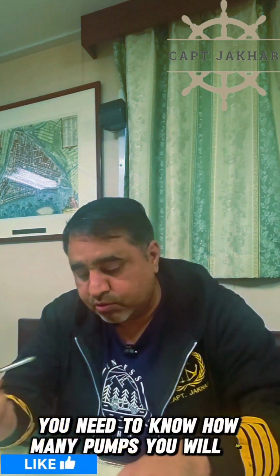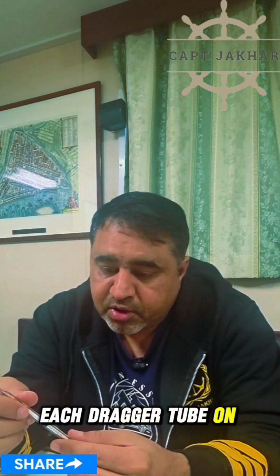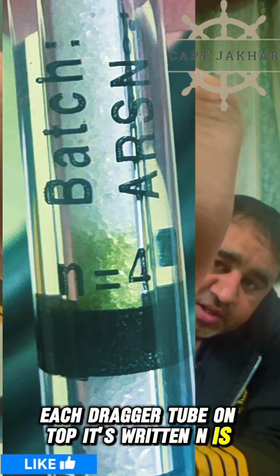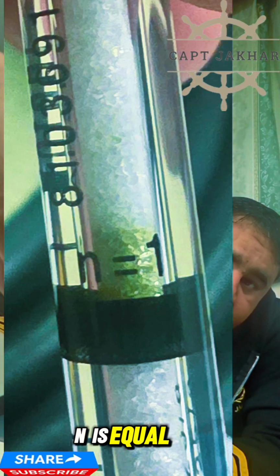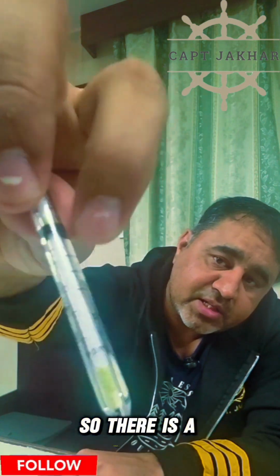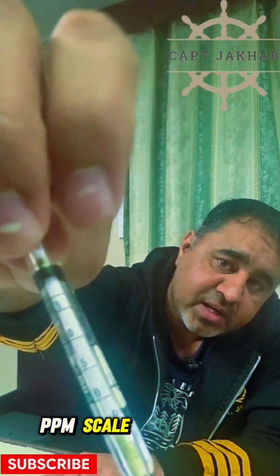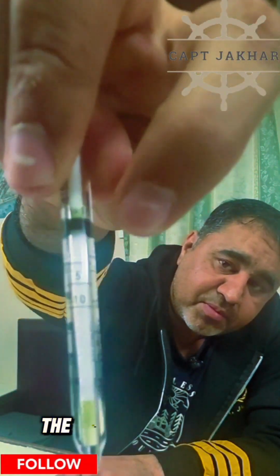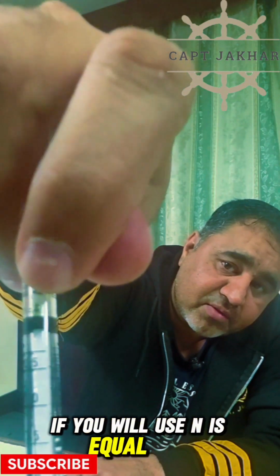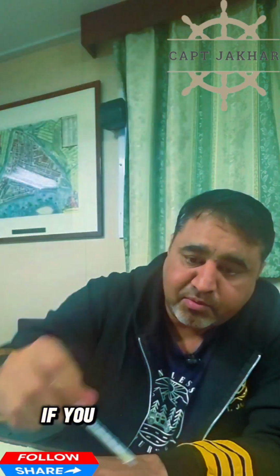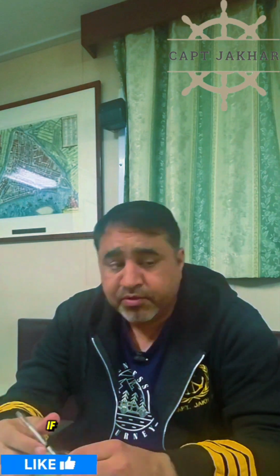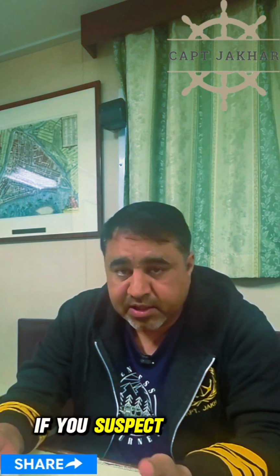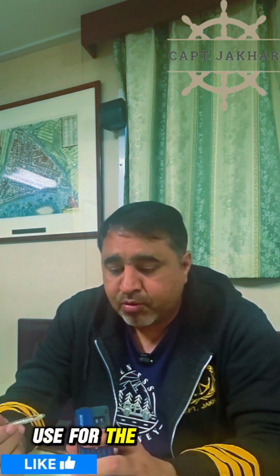Once you put the Drager tube, you need to know how many pumps you will do. On each Drager tube, on top, it's written N equals 4, N equals 1. It will be different for different tubes. There is a concentration here, a ppm scale. If you use N equals 1, the ppm measurement is like this. If you use N equals 4, the ppm will be like this. If you have more ppm, you need to use fewer pumps. If you suspect there is less ppm, use more pumps.